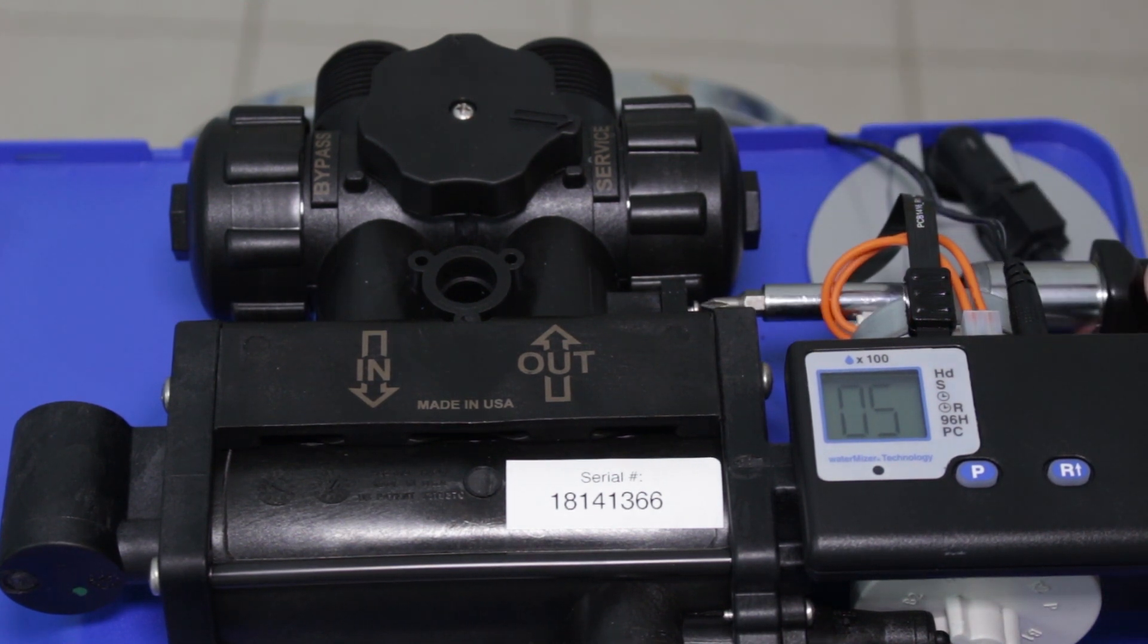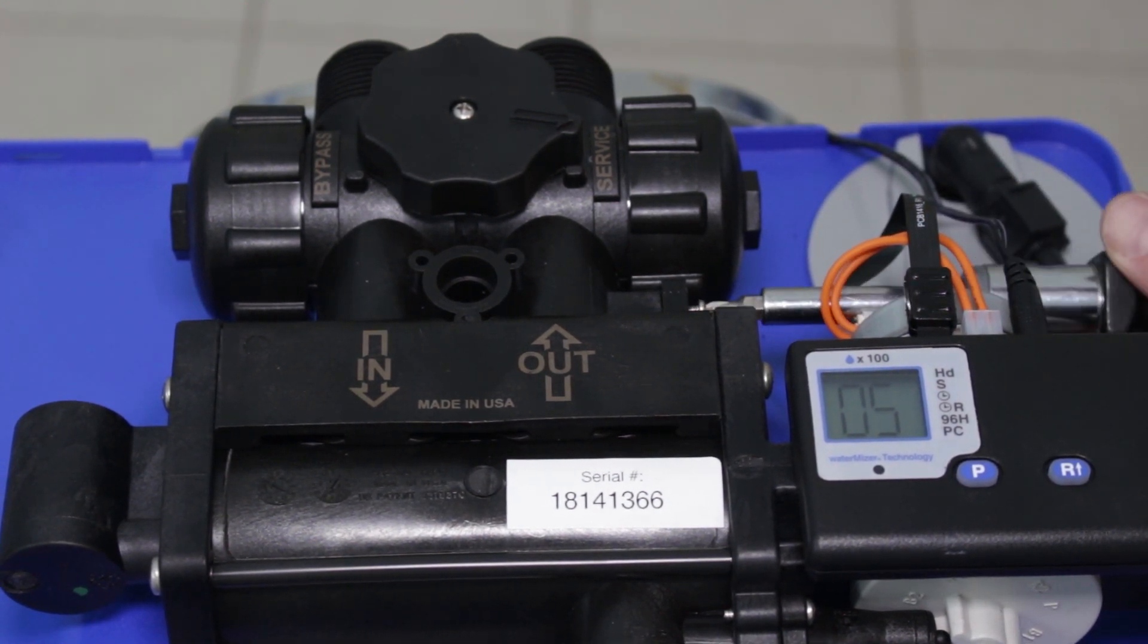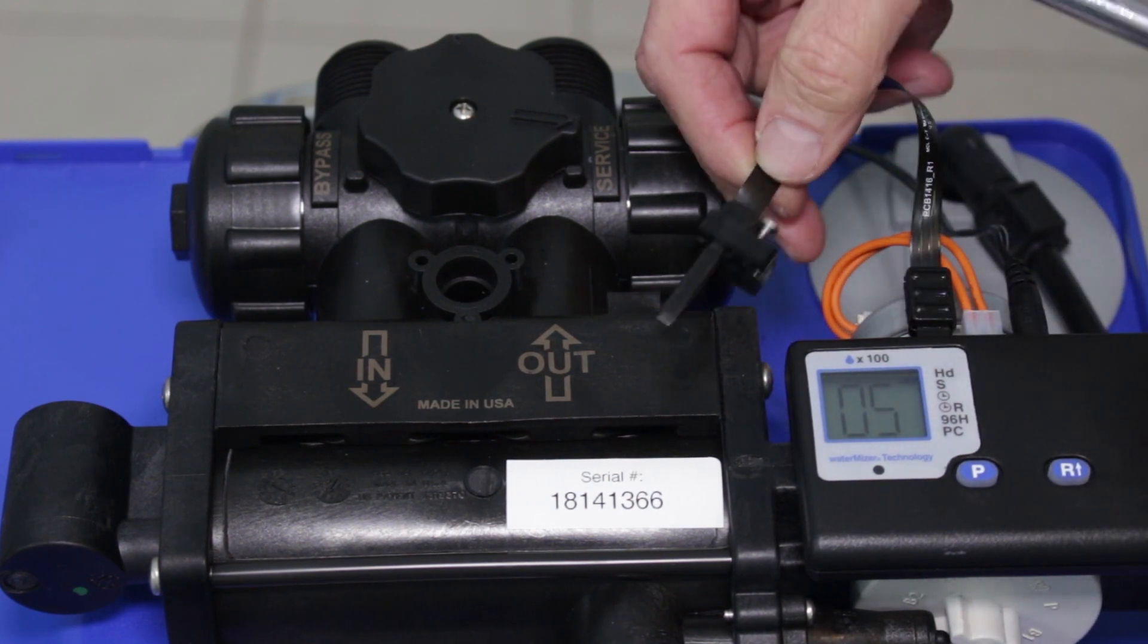What you would do is remove the flow sensor, which is inside here. This is one little screw that you need to pull out. And then when you pull it out, this is the flow sensor here.